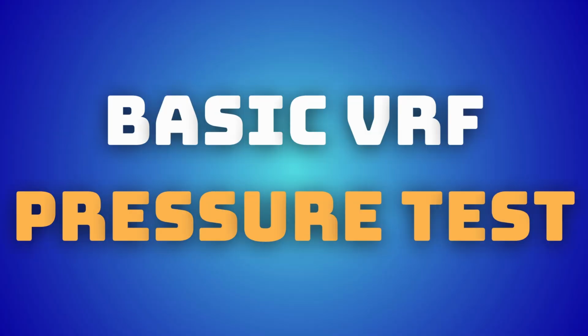Assuming I have a system that's already fully recovered and maybe I've done some repairs to it and I'm just looking to do a base pressure test, the bare minimum I'm going to do is get 300 psi of nitro in it. And sometimes I'll take the time to actually pull a slight evacuation on the system to get some of the atmosphere out. That'll improve the accuracy of the test, but it's not dramatic, especially if you know how to adjust for your temperature changes in terms of ambient.